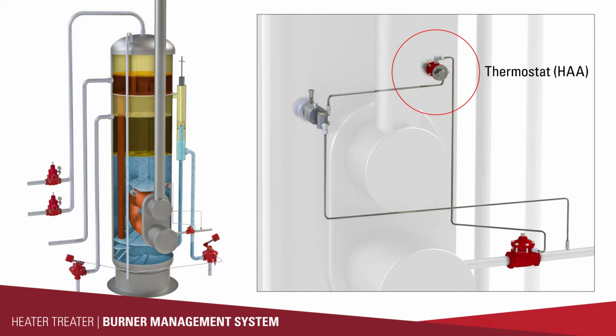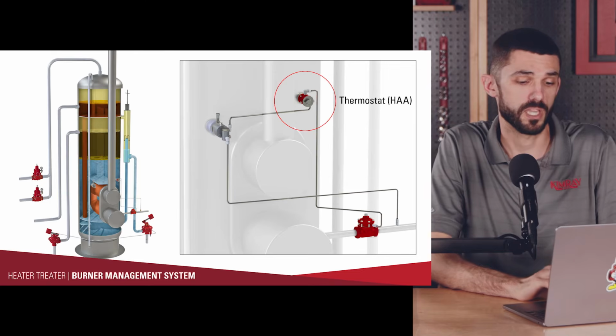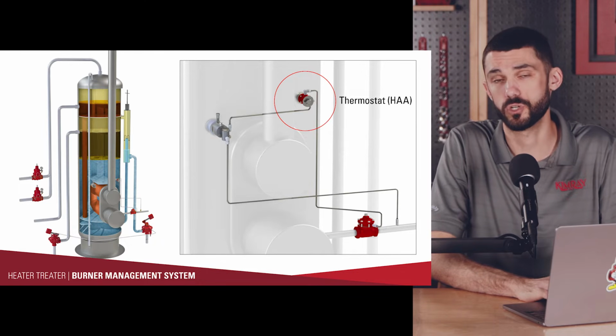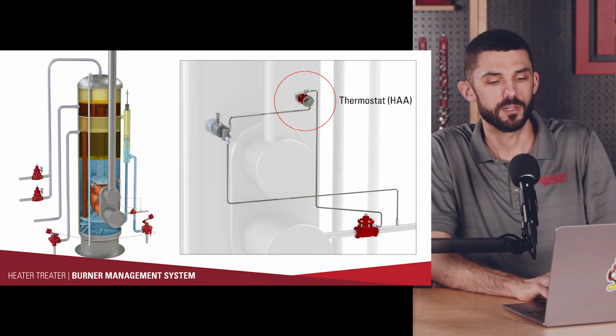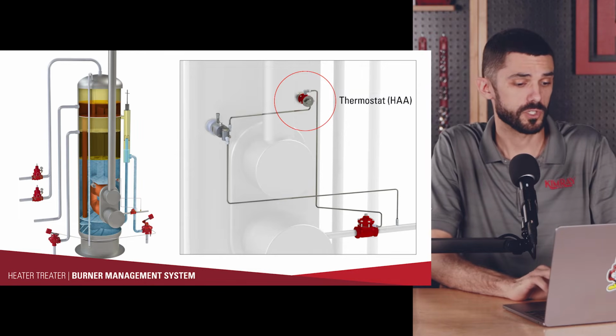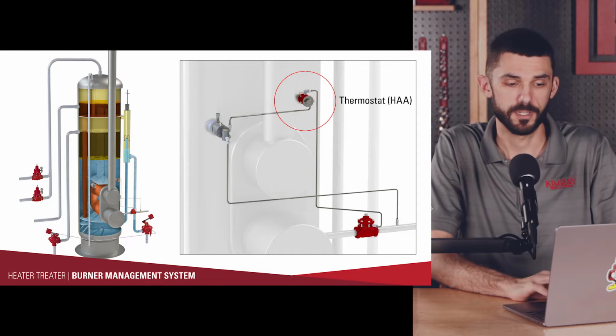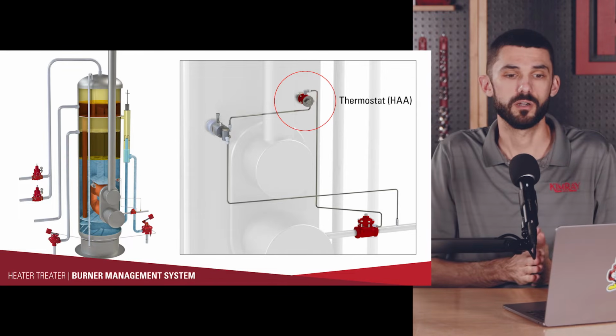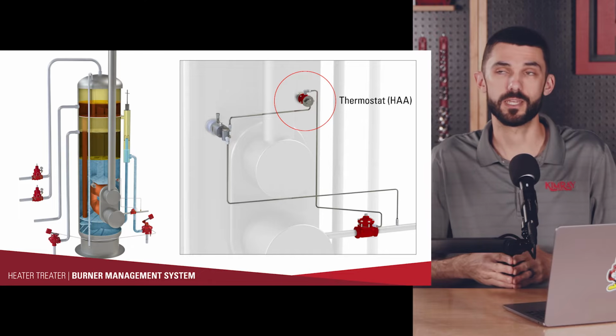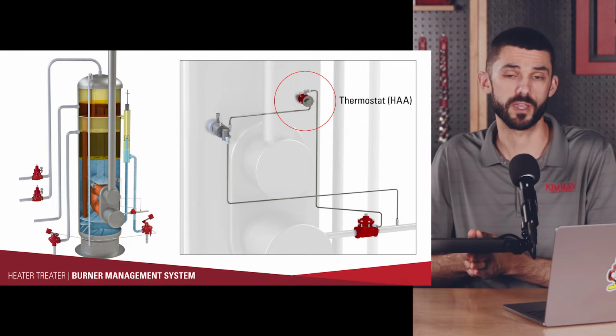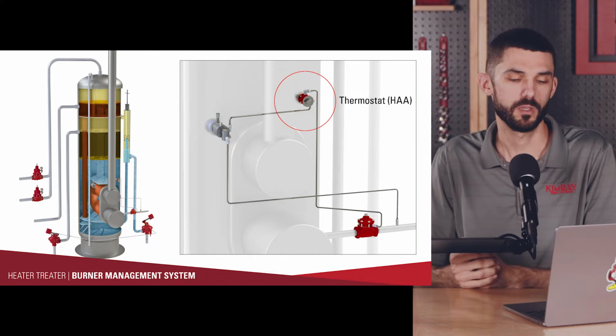The different pieces of equipment that our thermostat is typically used on. Here you can see it's being used on a heater treater, but any heated piece of equipment can use the thermostat to control the temperature inside of that vessel. So we've got heater treaters, line heaters, and any heated vessel, outside of maintaining and controlling the temperature of a fluid bath or a liquid. There are a few applications where you can use this to control and monitor gas temperature.